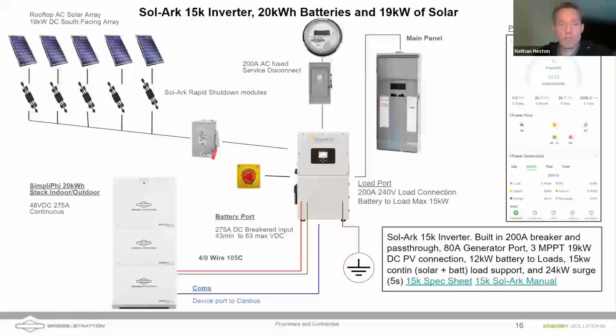Of course, typically you would be sizing that solar to come in to cover the loads and provide some extra power. So generally you'd be able to charge the batteries, but you can do this with small systems. Small solar, the battery system, of course, has to have enough power to be able to power the inverter. I also want to point out that you can have AC or DC coupled solar with this Sol-Ark, and you could have both. You could have up to 19 kilowatts of AC coupled solar and simultaneously have 19 kilowatts of DC coupled solar, although Sol-Ark recommends that you reduce the amount of AC coupled solar compared to DC coupled.